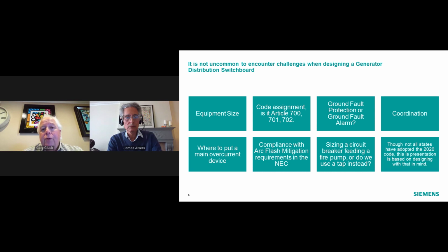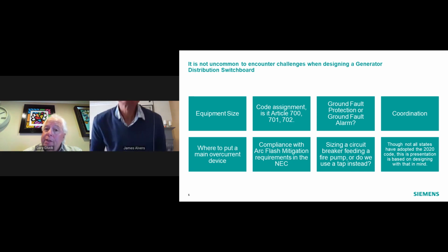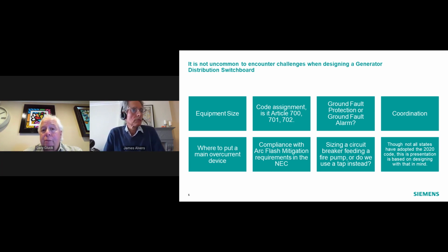Coordination. When we talk about coordination, it's typically in the context of selective coordination. The two areas where we're going to be running into this will be with emergency and legally required. We need to appropriately pick the correct overcurrent device so that it coordinates with the downstream loads from the generator distribution switchboard. Then we come up with the main overcurrent device. If you have one, where does it go? The code is a little bit vague as far as that goes, and we will cover that.